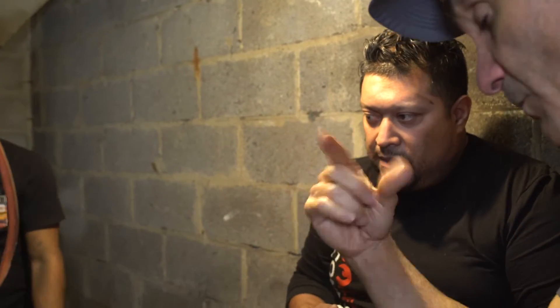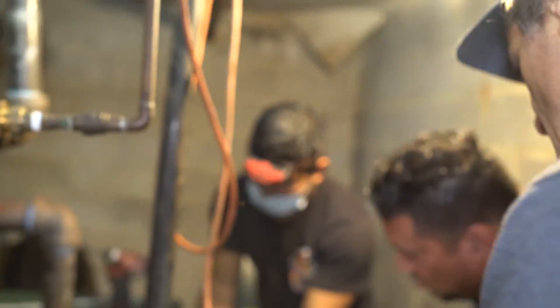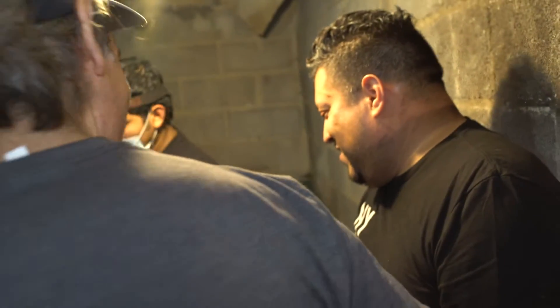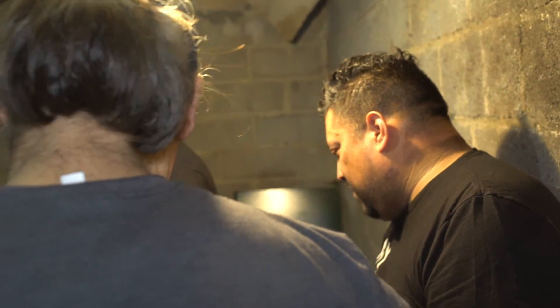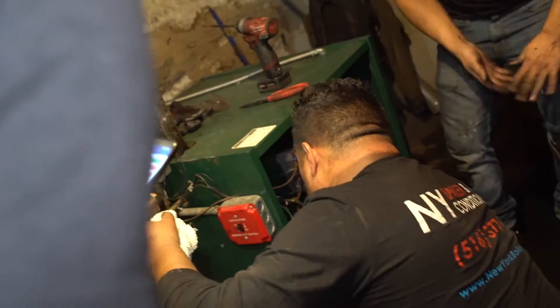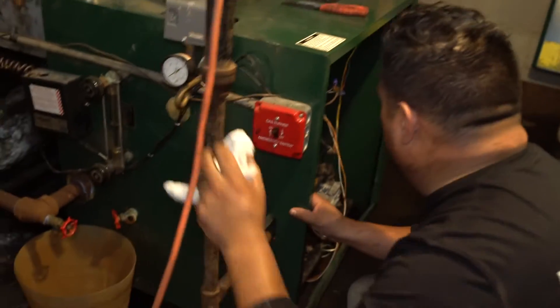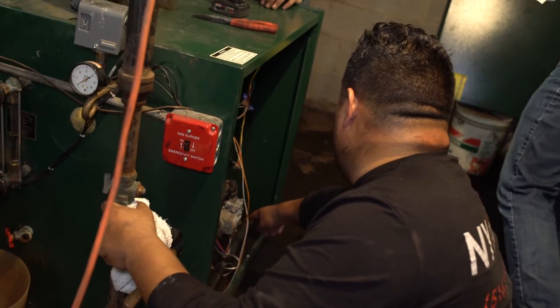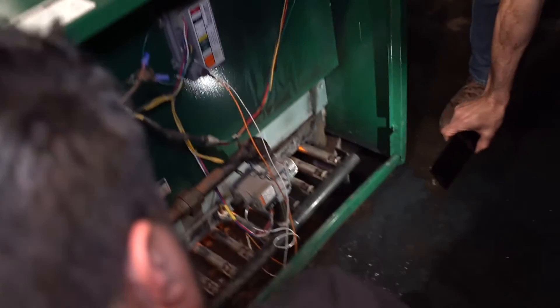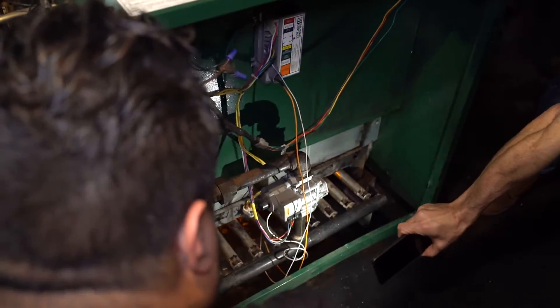Can we check the damper? I think that had a problem too. We'll disconnect it and we'll turn it on — I jumped it right now, that's what it turned on. Maybe you have to raise it up a little bit. Right now, so far so good. It's definitely the burner, because you can see it on the bottom — when you check the last two or three burners, you can actually see gas, a fire coming up on the side, and they're not supposed to.